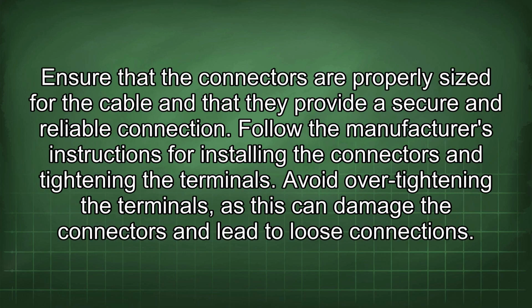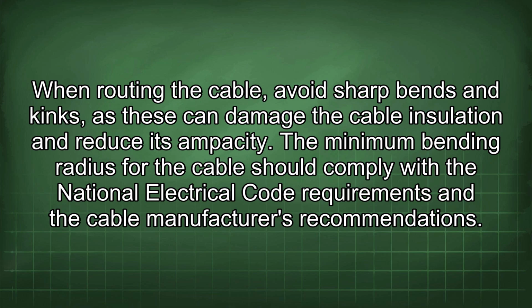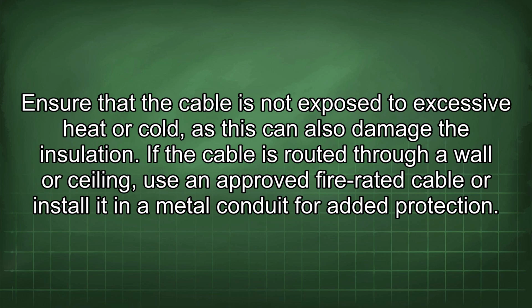Ensure that the connectors are properly sized for the cable and that they provide a secure and reliable connection. Follow the manufacturer's instructions for installing the connectors and tightening the terminals. Avoid over-tightening the terminals, as this can damage the connectors and lead to loose connections. When routing the cable, avoid sharp bends and kinks, as these can damage the cable insulation and reduce its ampacity. The minimum bending radius for the cable should comply with the National Electrical Code requirements and the cable manufacturer's recommendations. Ensure that the cable is not exposed to excessive heat or cold, as this can also damage the insulation.